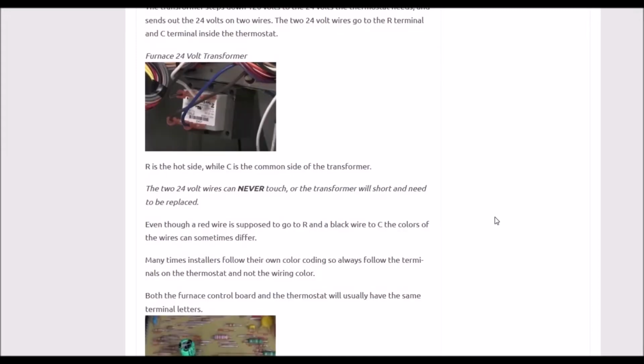And this small little transformer is a pretty simple little device. Like I said, it'll just have 120 volts on one side and 24 volts on the other. And it's really easy to test with the meter. It's AC voltage, so be sure to have your meter on AC voltage, and you'll just read 120 on one side and you should be reading 24 volts on the other side. They don't usually go bad, but they can go bad occasionally, so it's something to keep in mind, mainly if you're not getting 24 volts AC to the thermostat.